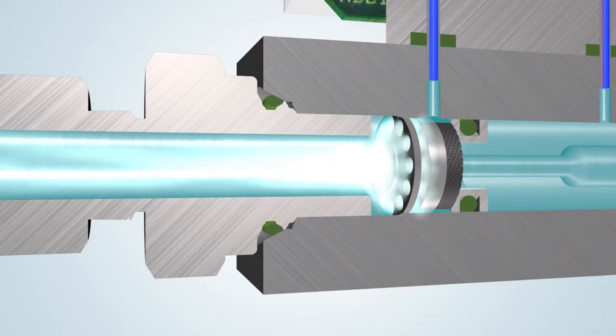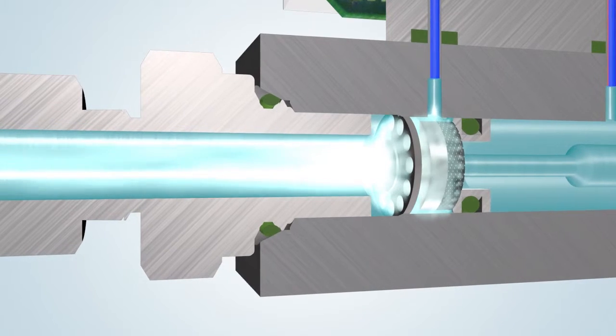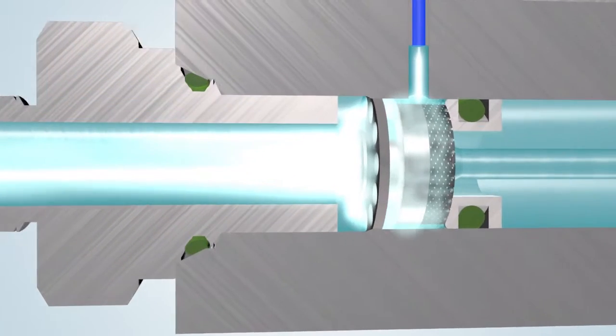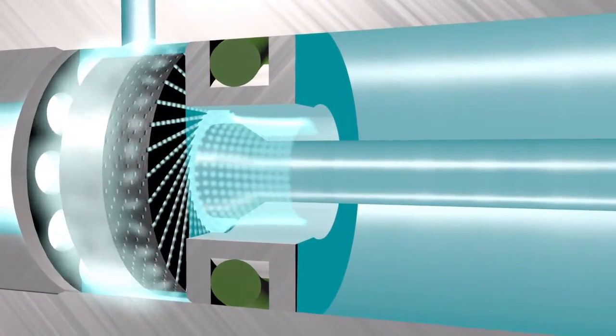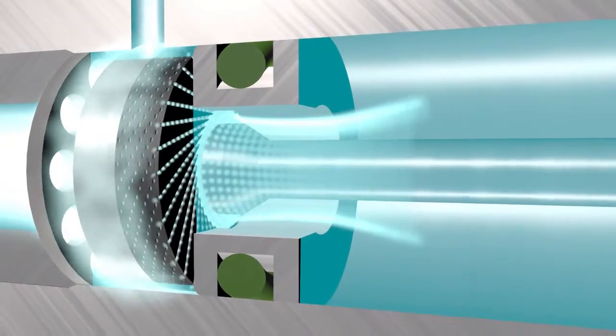The gas flows through the laminar flow element which serves as a perfectly predictable flow resistance. This makes it possible to build and calibrate an instrument for use on nitrogen and to model it for any other gas.